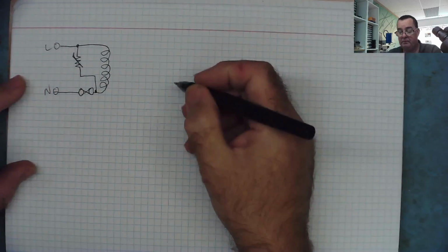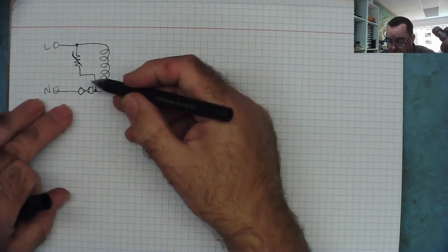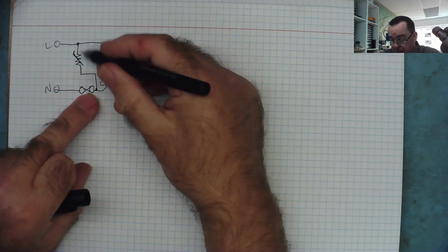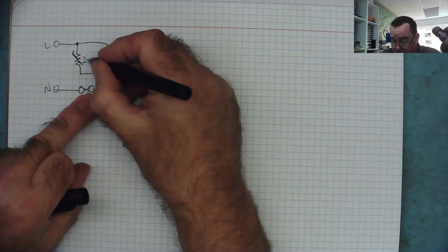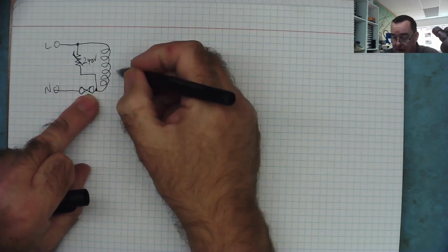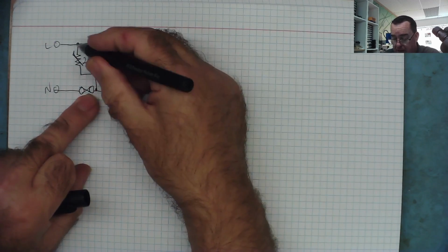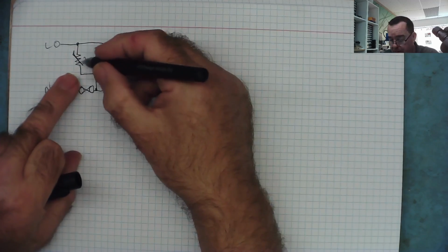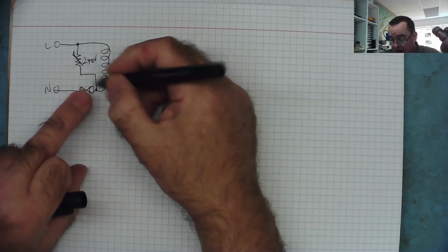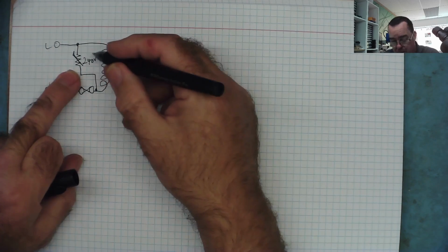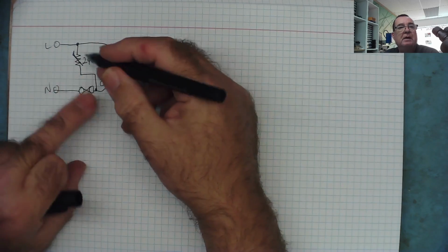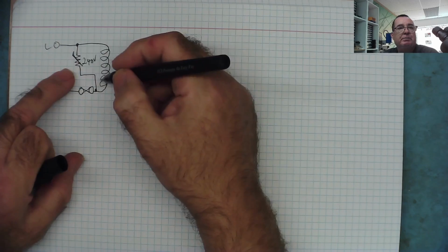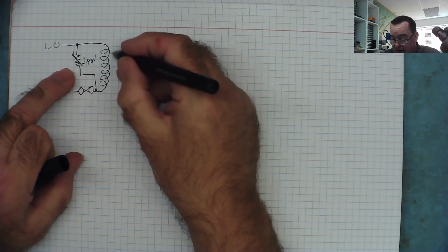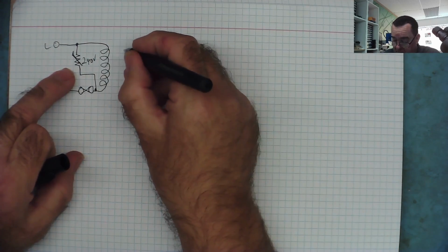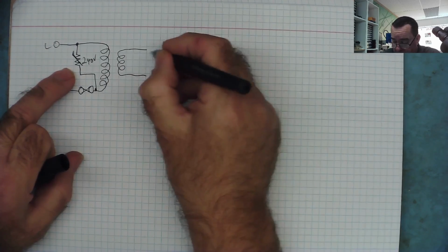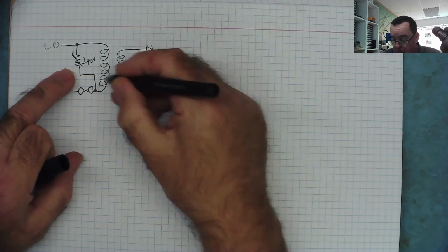So that's where the Varistor goes, and the idea is that if more than the rated value, in our case 240 volts, appears across here, this conducts and effectively blows the fuse, and usually blows the thing as well, or damages it. So in this case you normally have to replace it. They usually go short circuit. It looks like ours hasn't gone short, but it's in some way blowing the fuse, like it's breaking down under voltage. That's A, to protect the primary of the transformer, and B, to protect whatever's connected to the output of the transformer from too much voltage.